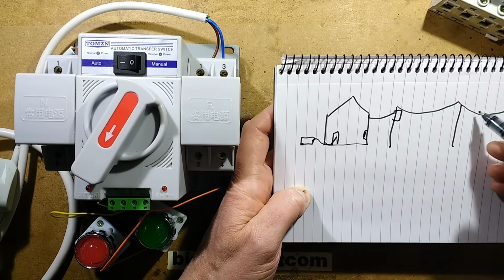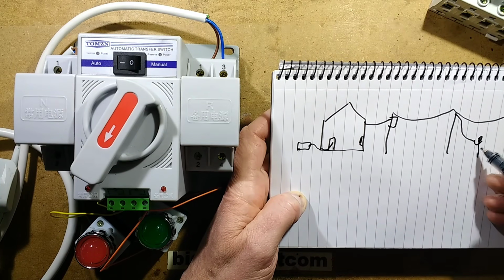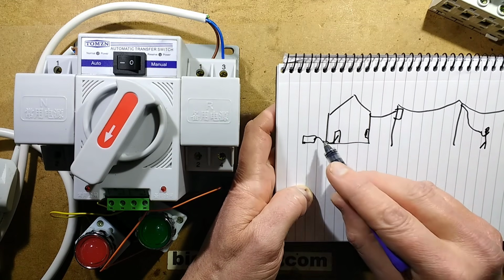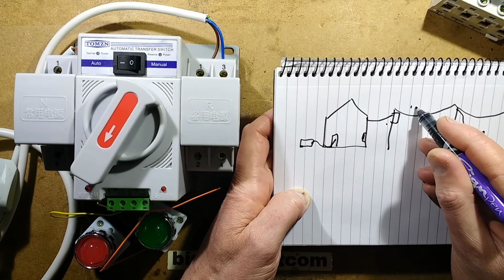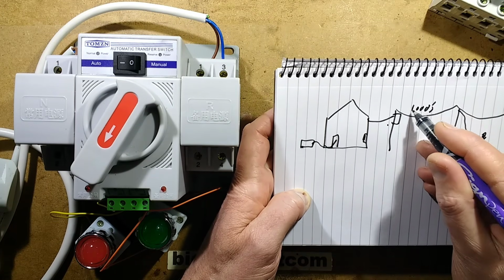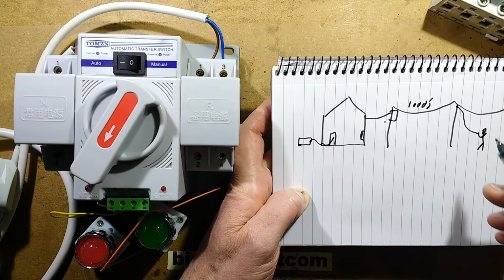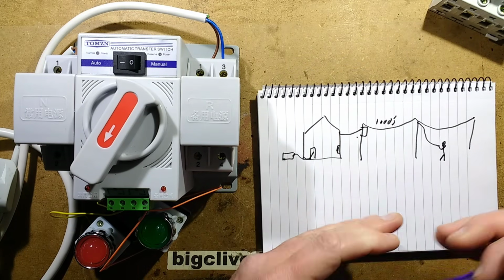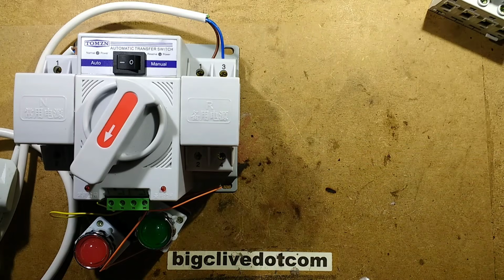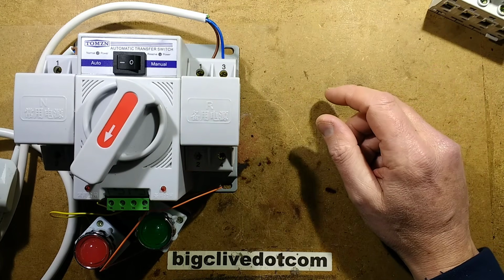But worse still, if you've got a cable down and there's someone actually working on the restoration of the power, then if you backfeed into this transformer, you can actually step the voltage up, and you can end up with thousands of volts on the overhead lines because it's stepped the voltage up. And the people working on it are actually at risk of fatal electrocution if you do that. And this has happened. It has happened quite a lot, where people have been working the lines and suddenly they convulse up because someone has backfed the line from a generator. So you have to be very, very careful in that approach.